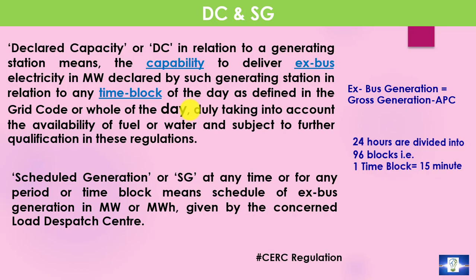The technical capability of a unit in terms of ex-bus generation is generation capacity minus normative APC, meaning normative auxiliary power consumption or auxiliary energy consumption. The auxiliary power consumption is the consumption of electricity for its own auxiliary equipment. This auxiliary power consumption varies from unit to unit. So CERC provided the standard APC, which is called normative APC.